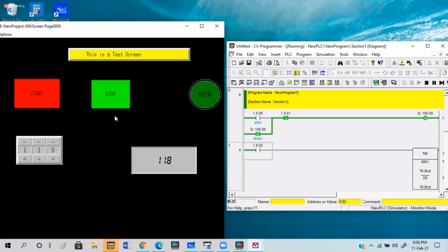So that is, in briefest introduction, what we need for you to deal with. Only thing, like I said, you'd have to go into the memory and change the memory for the CX programmer to decimal, because the default setting is hexadecimal, so that what is input and what is displayed is going to be the same.